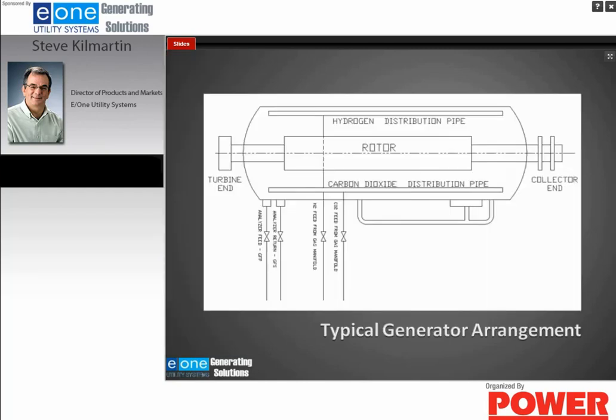This is a section view of a hydrogen-cooled generator. We're going to talk right now about the hydrogen purging process. But before that, the 2 pipes exiting the generator on the lower left-hand side, this is where the analyzer gets its sample during normal operation. And those 2 lines are coming from the generator fan pressure and the generator fan suction.